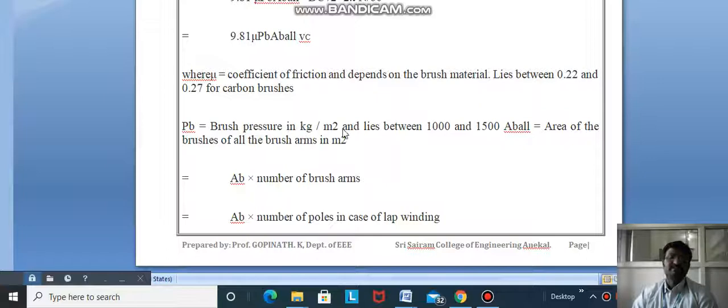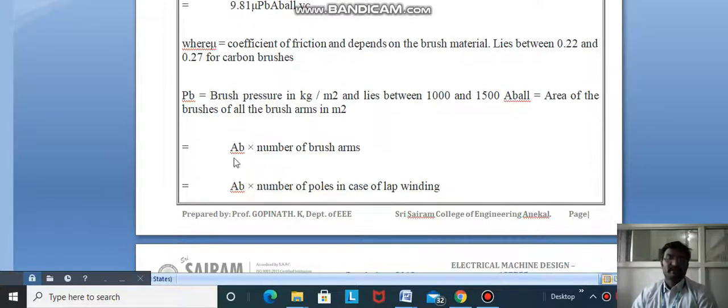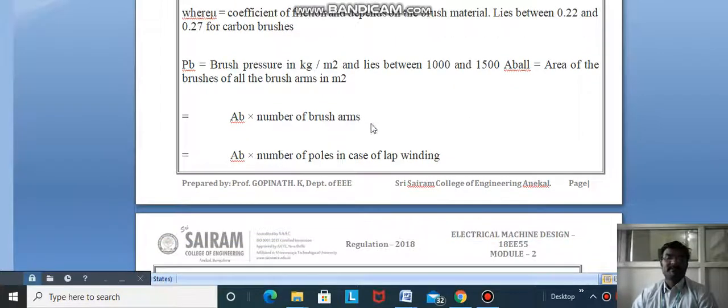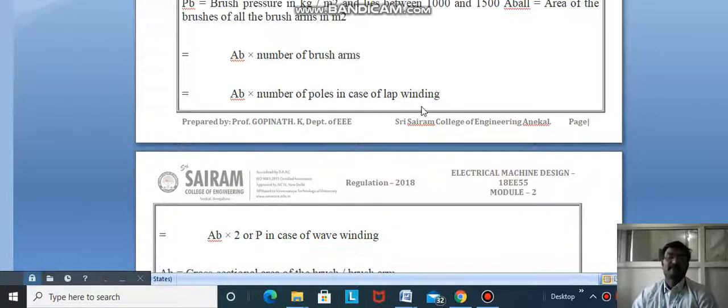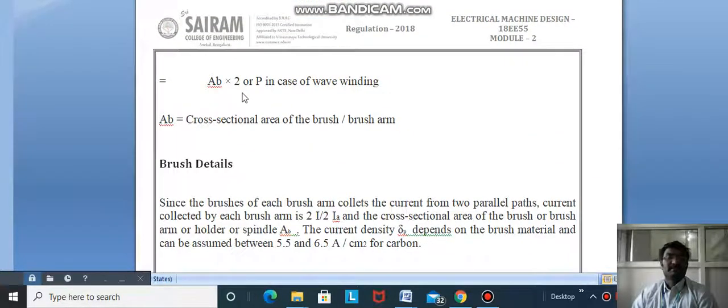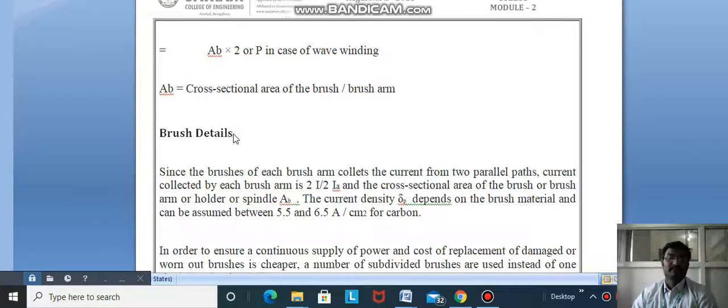μ depends on brush material and lies between 0.22 and 0.27 for carbon brushes. Pb is brush pressure in kg per m² and lies between 1000 and 1500. Ab is area of brush arm in m², times number of brush arms: 2P for lap winding, 2 for wave winding.